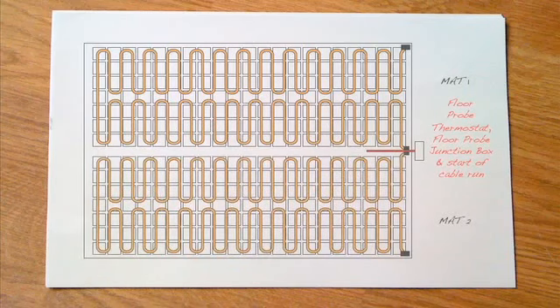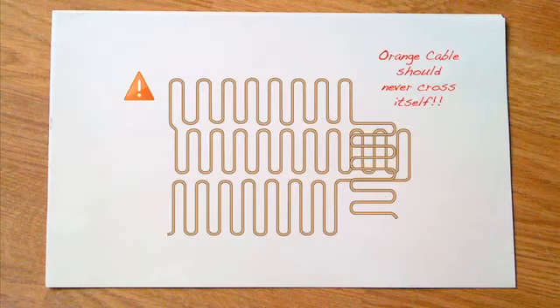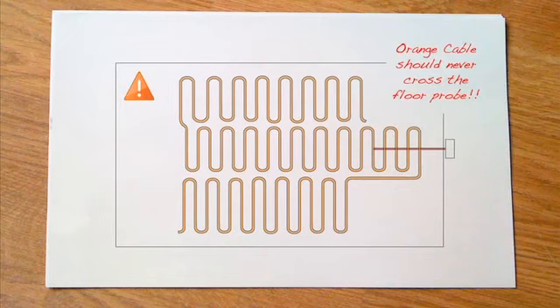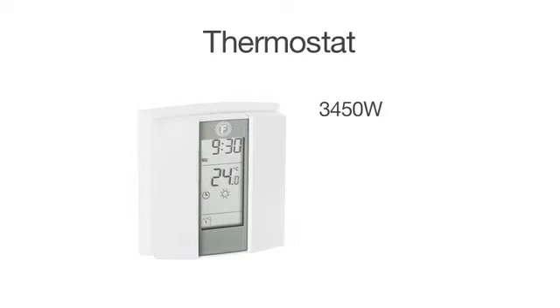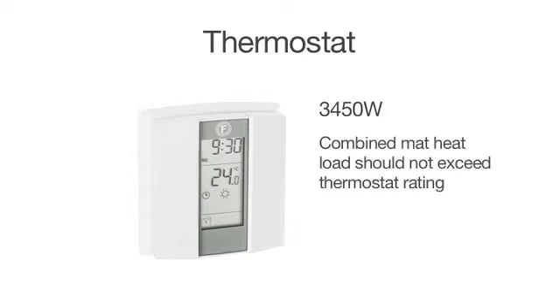Multiple mats are joined in parallel. The orange heating cable should never cross at any point. The orange heating cable should never cross over the floor probe. A single thermostat can be installed to control multiple heating mats. However, the combined heat load should never exceed the rating of the thermostat. If this does occur, a suitably rated contactor should be installed.